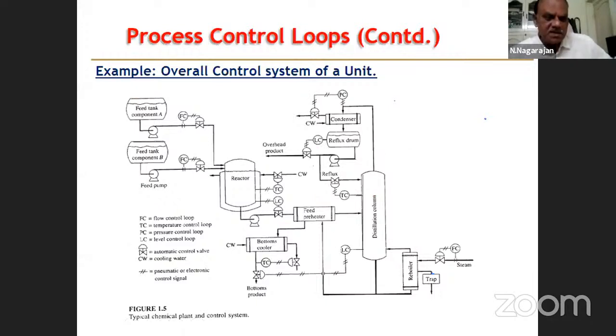right from the separator tanks and then to the two raw materials, component A and component B. On flow control, they are fed into the reactor. Reactor is heated by steam jacketed. So you have a temperature control on the jacket side for controlling the temperature of the reactor. And then the outlet from the reactor, there is a level control, and then this goes to the feed heater, it goes to the distillation column.